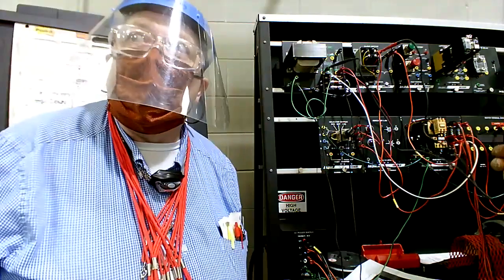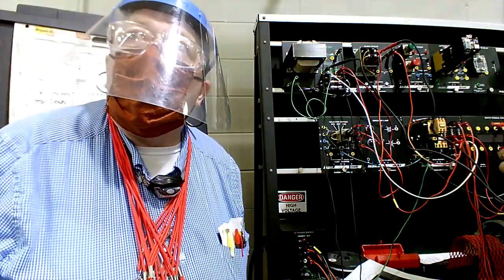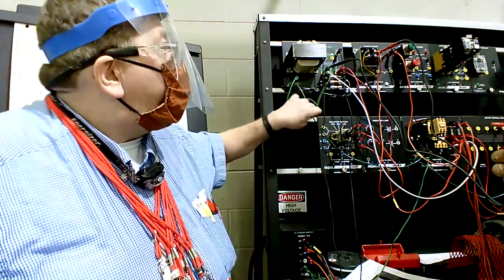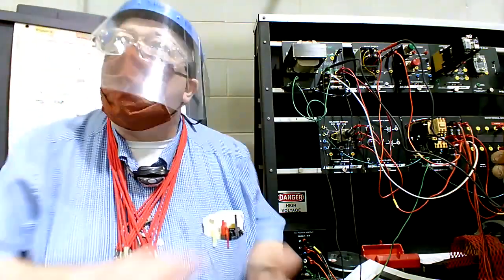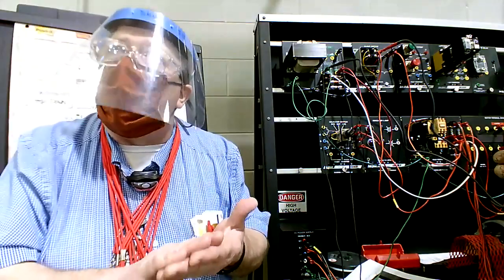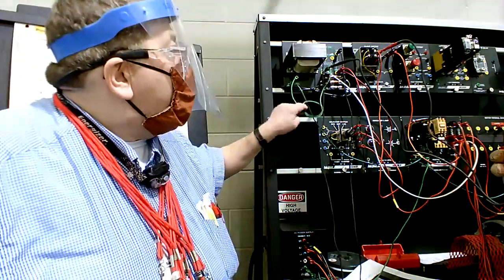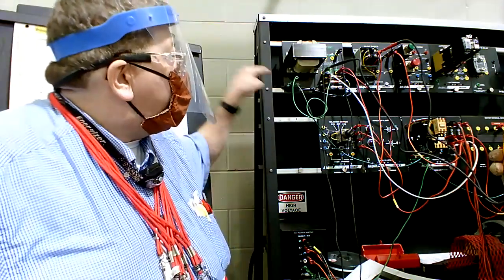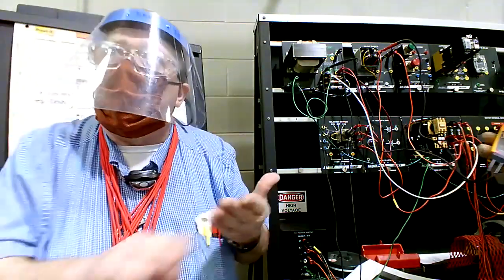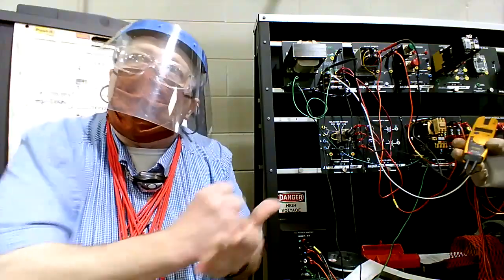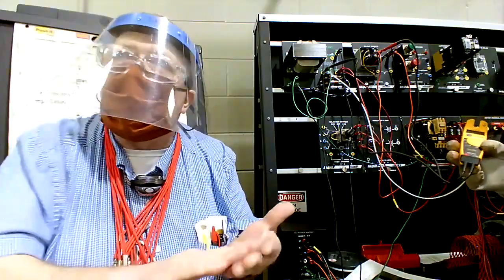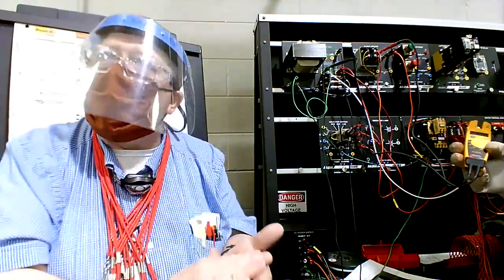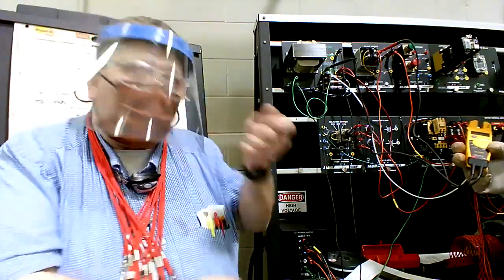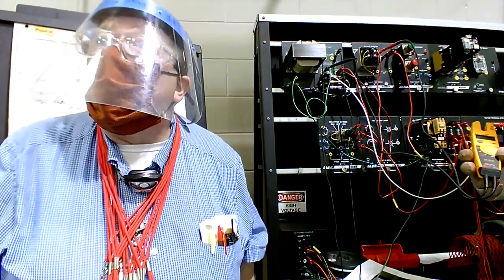You're saying if the ground is hooked up to the neutral? Yeah, if ground is hooked up to the neutral, but you have a rusty connection, a bad connection that's become rusted or corroded. Disconnect the ground from the neutral? Yeah. I'm telling you that if it's hooked to ground but it's a bad, corroded connection, you'd have to take it off and scrub it with sandpaper or something like that to clean it, and then reconnect it to be able to use ground as a reference point. You know what I mean? Just still use the neutral.